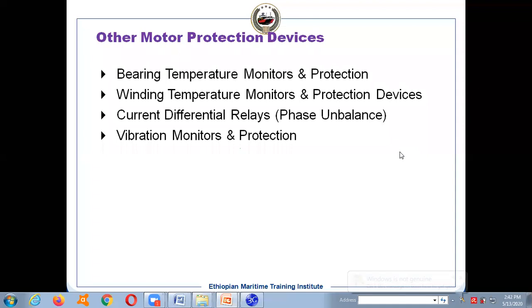Thermistors are placed inside the windings. Whenever the temperature goes high, you cannot start the motor, or the motor will trip. Mostly you'll find this type of winding temperature sensor in transformers, generators and motors. Inside the winding, you'll find the thermistors. In generators and transformers, you'll find maybe two sets, with one on standby in case the main thermistor fails. Heavy duty motors also use thermistors for winding temperature, though not normal motors.